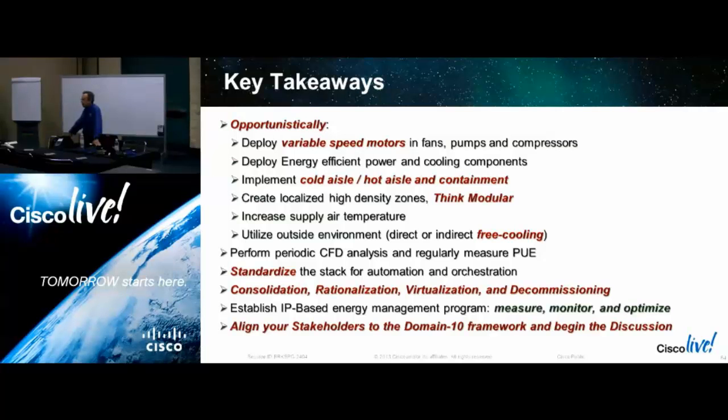Part of it depends on the gear you're deploying. If you have a mainframe, a lot of mainframes still require that underfloor for a variety of reasons. But a lot of shops are going to a solid floor. A couple of customers I've dealt with, I'm sure, Chris, you've seen them as well. The case for having raised floor is pretty weak nowadays as a general rule. And of course, the exceptions prove the rule. But there are a lot of ways to do efficient cooling and distribution and all the rest without a raised floor. In fact, our data centers don't have raised floor, the new ones. Yeah, the new ones don't.